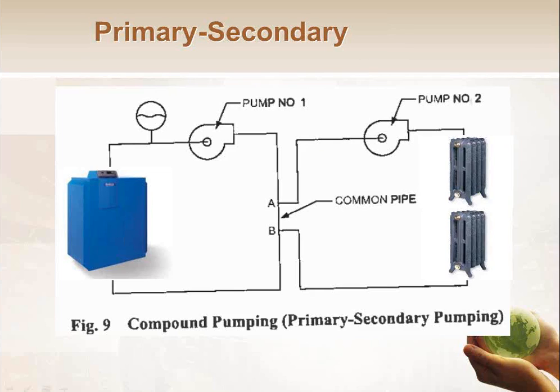On the left side of the drawing here, we got our primary loop, right? So that's this guy here, leaves the boiler, goes through the pump, circles around, goes back into the boiler. That pump is sized just to handle the pressure drop of this boiler's heat exchanger, as well as the small amount of piping here in the boiler room. He doesn't care about your house or your building or your campus or anything else going on in the building. That's not his problem. His job is just to circulate water through this one little loop in the boiler room, and he's sized just to make it through that loop and through that boiler's heat exchanger.